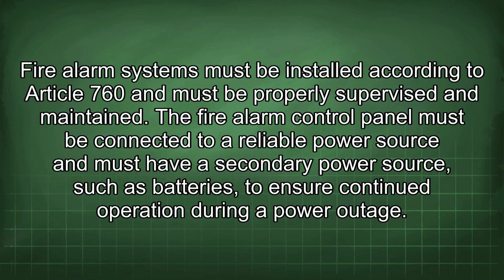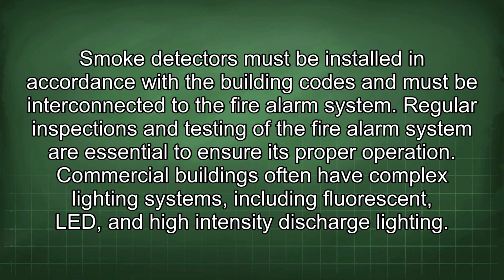The fire alarm control panel must be connected to a reliable power source and must have a secondary power source, such as batteries, to ensure continued operation during a power outage. Smoke detectors must be installed in accordance with the building codes and must be interconnected to the fire alarm system. Regular inspections and testing of the fire alarm system are essential to ensure its proper operation.